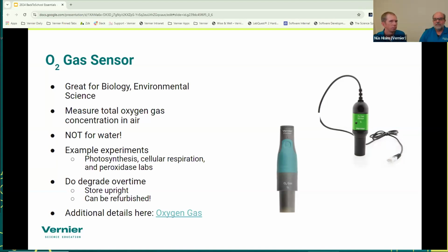The other thing to be aware of is that gel does degrade over time. After 3 to 5 years, you may find that you just can't get good oxygen data from your sensor. That's because the gel in the actual sensing element needs to be replaced, and we're happy to do that for you. There's a bit of a charge because we have to replace that sensing element, but it's much cheaper than buying a whole new sensor. And we have them in both the old style, the LabQuest style, that many people are familiar with.